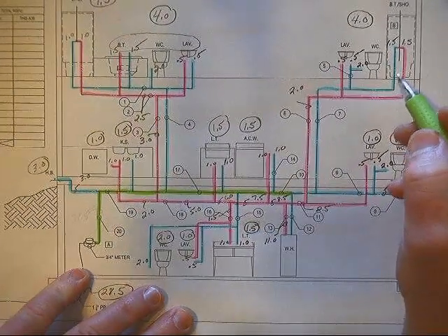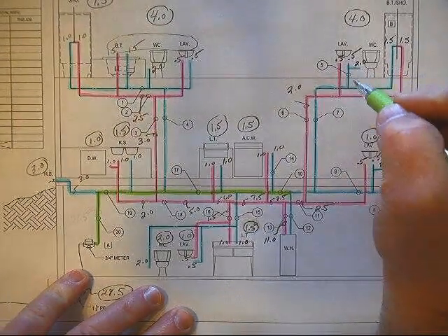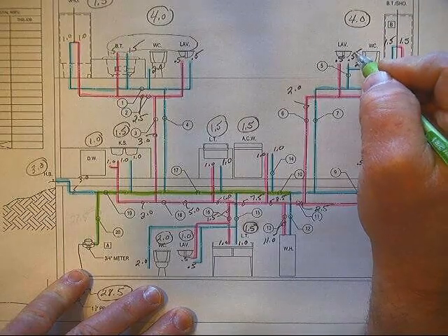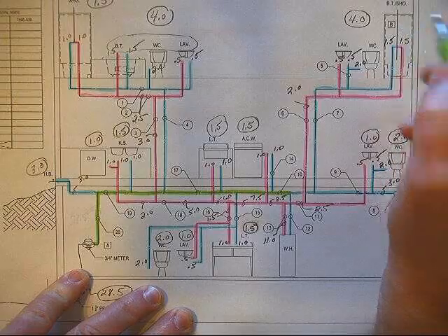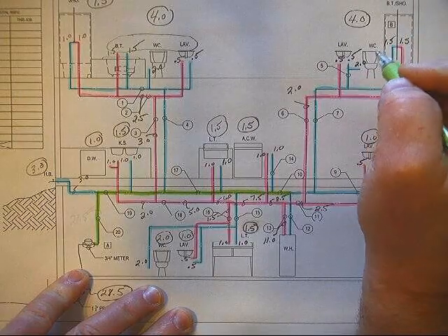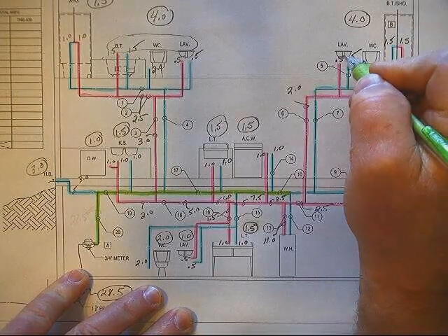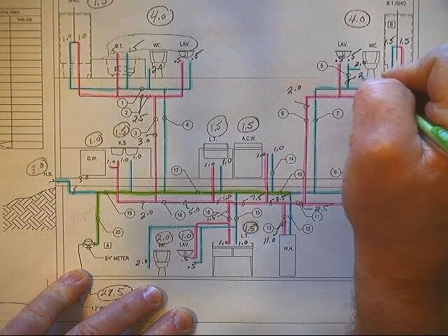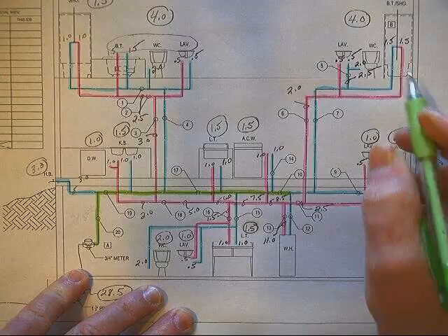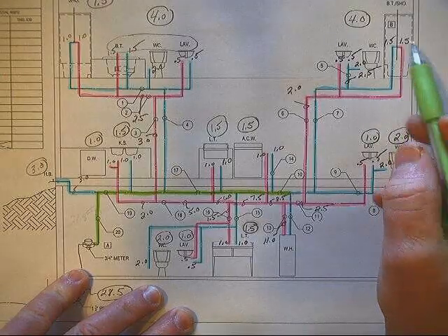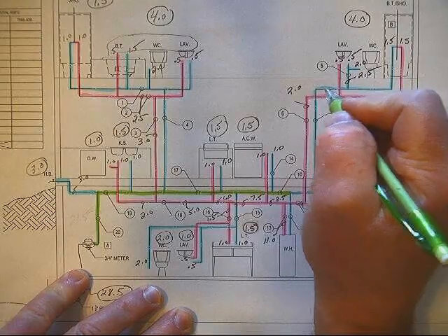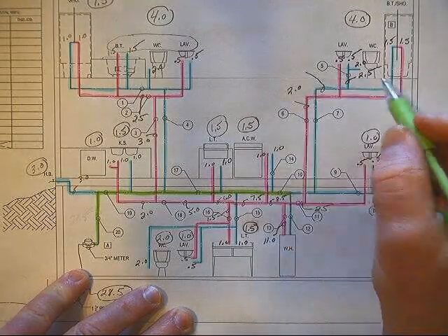We'll start up here at pipe number 5, which is right below the feed to the lav and to the water closet. So the water closet had 2 on it, the lav was 0.5, and so this piece of pipe would have 2.5 on it. The next thing that we will do is we'll take a look at this piece of pipe right here, and we'll put the load on that.